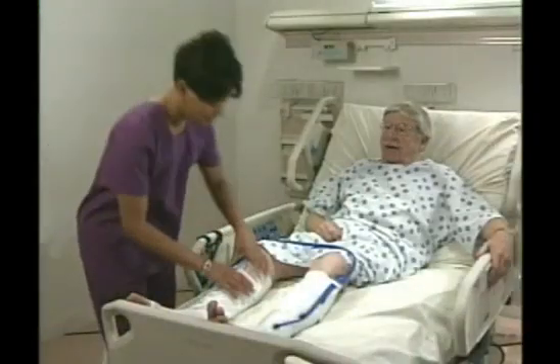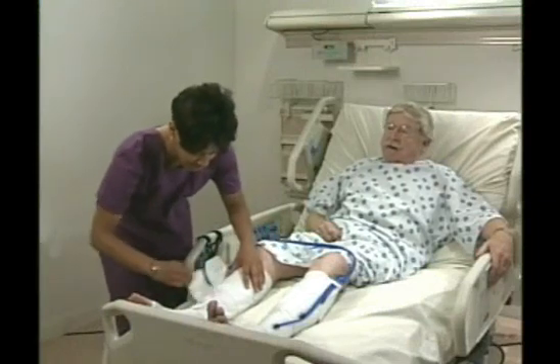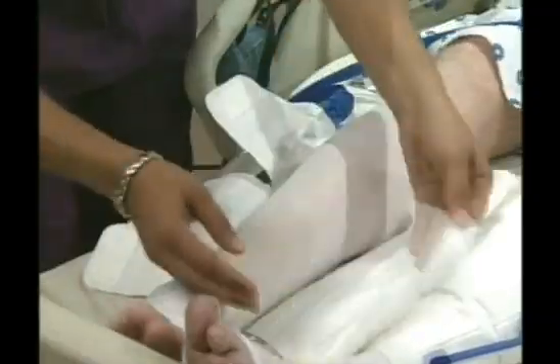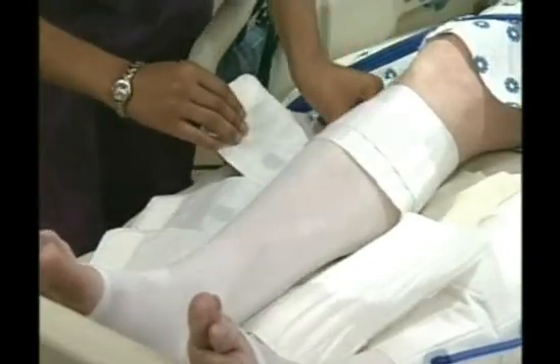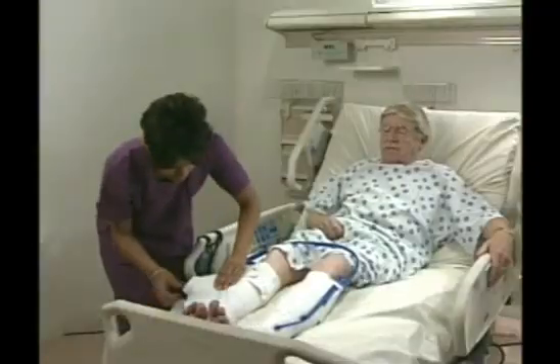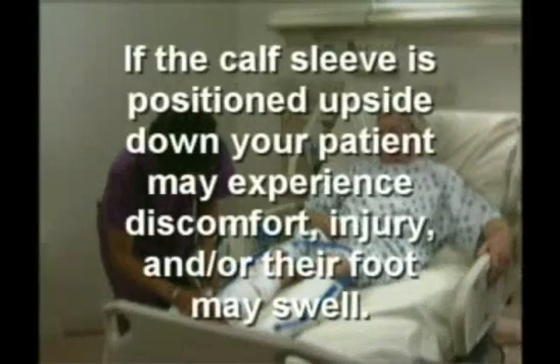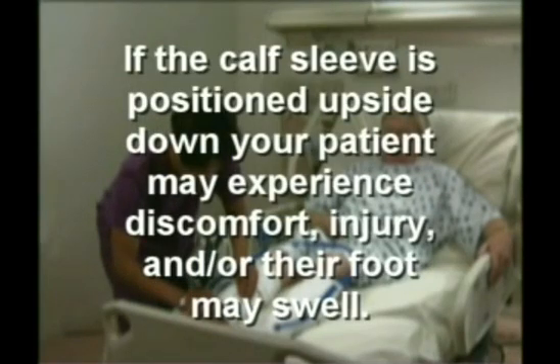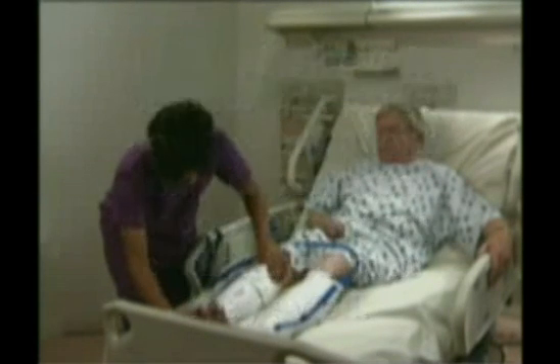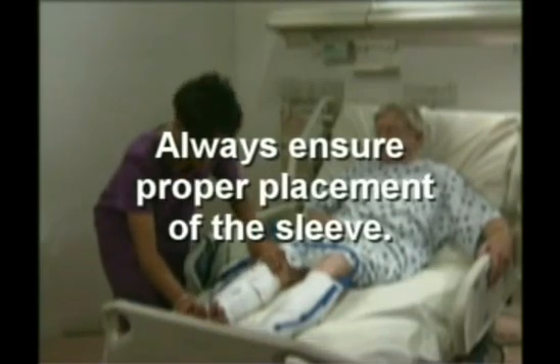Before we talk about setup and operation, it's important to point out a few precautions associated with the use of this device. Inspect the legs of patients using the device at least once a day for skin changes. If your patient has loss of or impaired sensation in their legs prior to wearing the device, double-check the positioning and proper adjustment of the sleeve before and during operation. If the calf sleeve is positioned upside down, your patient may experience discomfort, injury, and/or their foot may swell. Always ensure proper placement of the sleeve.